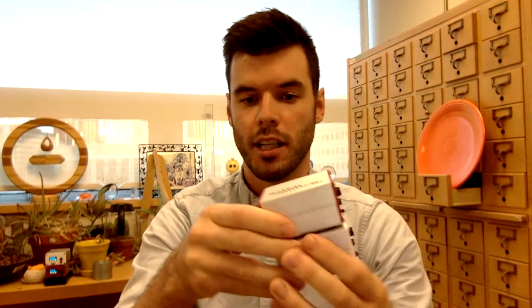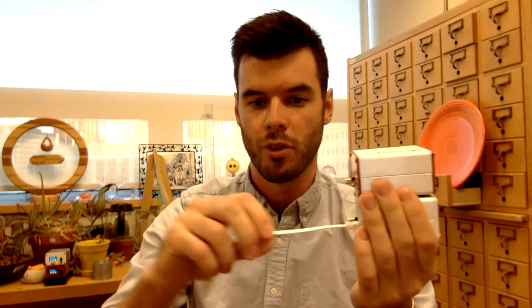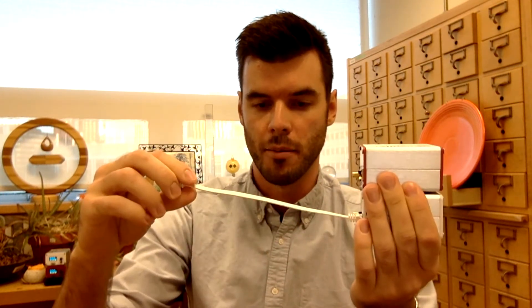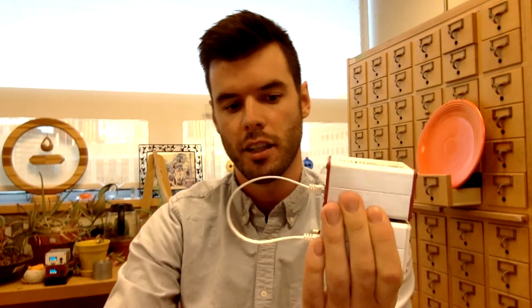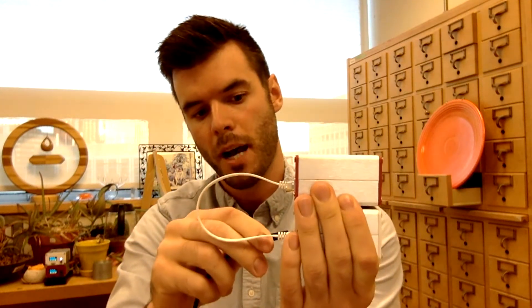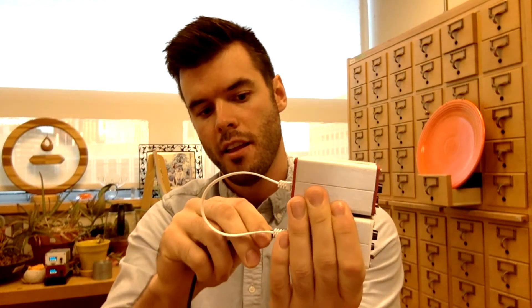Besides background radiation, we're actually aiming to measure a lot of things associated with cosmic ray muons, and that's why we've supplied two cosmic ray muon detectors to you. The cosmic ray muon detectors can be connected together through the coincidence cable. This is just a standard Ethernet cable. Once they're connected together and a single one of them is powered on, they will both boot up in what's called coincidence mode.